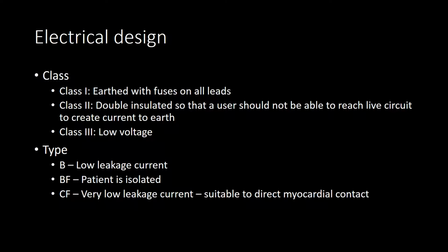Type is defined by leakage current. Type B is a low leakage current. Type BF is that the patient is isolated from Earth, so that if there was a leak, it won't go through the patient—it will still need to go back through the circuitry.